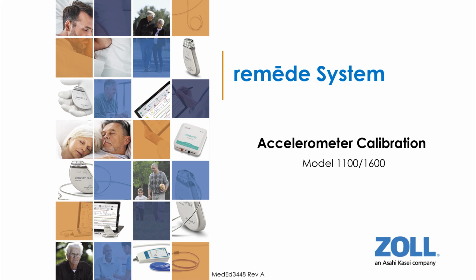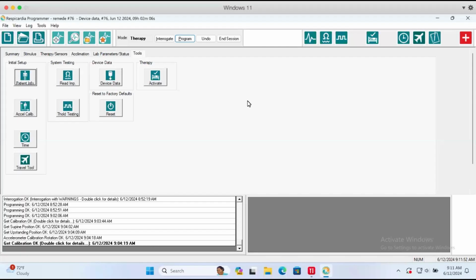Accelerometer Calibration on remedē models 1100 and 1600. How to calibrate the position sensor within the implanted device. These steps are after initial interrogation of the device. The position sensor calibration is essential for determining the patient's sleeping position and posture/pitch.